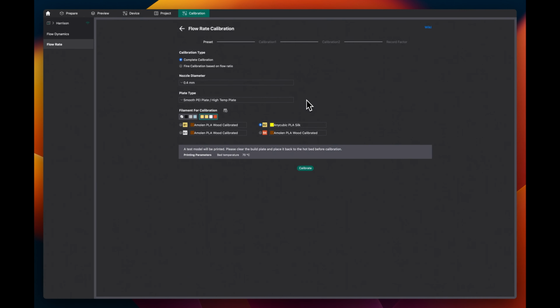It does it twice, so you don't have to do it twice, but I do. So you do it once, determine that's the best, then it bases the next set of calibrations on the setting you last chose, and then when you determine for yourself which one's the best flow rate calibrated square, you tell the system that, and it records it in your filament.